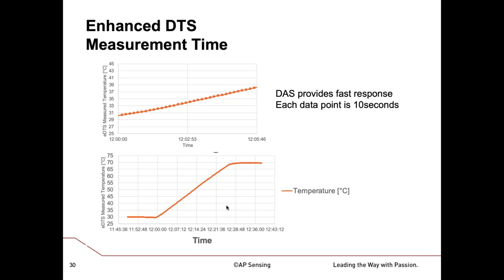Although the DTS is producing a measurement every 30 minutes at these long ranges, this is actually showing the DAS output every 10 seconds. As the temperature ramps up from 30 to 70 degrees, you can see a really nice ramp, and the top plot is a zoom-in of that ramp showing what the DAS is providing every 10 seconds. So not only do you get a better temperature resolution on your trace, you also have the ability to check temperature every 10 seconds — a much better temperature resolution and a much shorter effective measurement time.